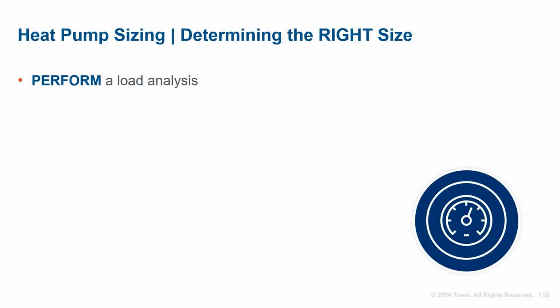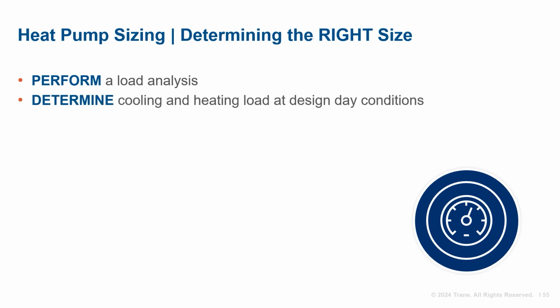Determining the right size for a heat pump isn't completely straightforward because the refrigeration system is sized for both cooling design and heating design with the possibility of needing auxiliary heat. However, there is a general method to guide you in selecting the appropriate size. The first step is to perform a load analysis. Based on the output, determine the necessary cooling and heating load at design day conditions.